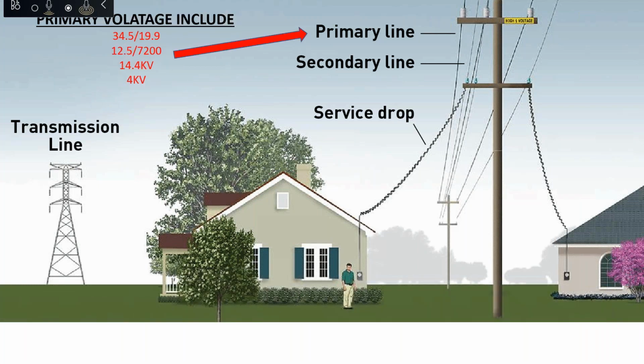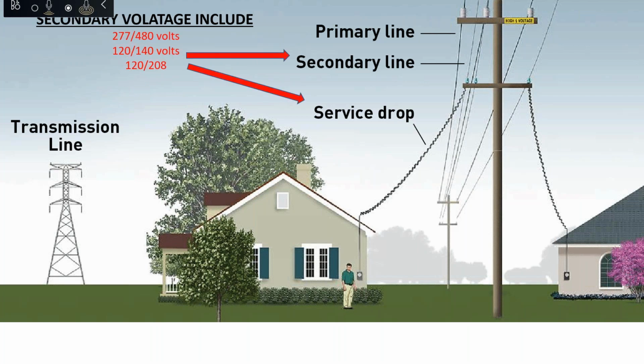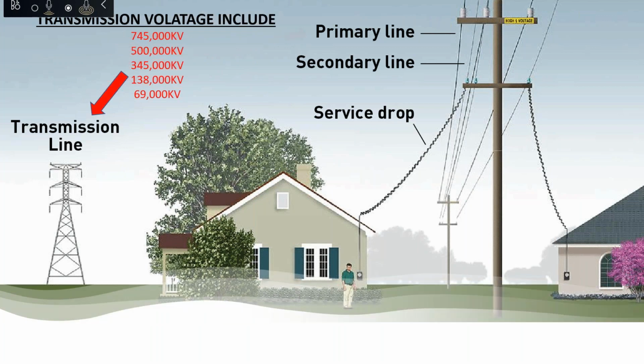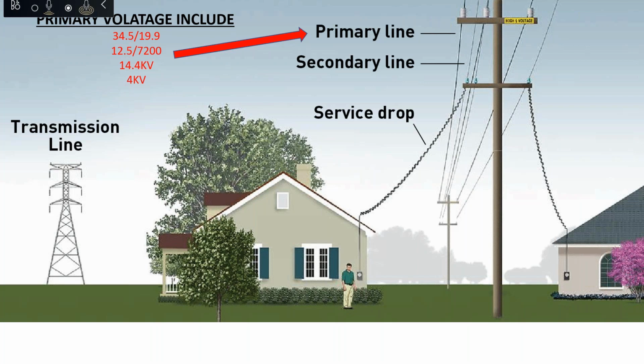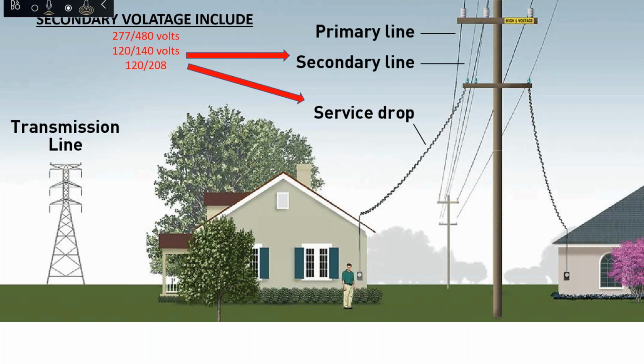But when we get down to our distribution voltage for our primary, 34.5 and 12.5, there's a lot more amps on that line. Amps are really the dangerous thing about electricity that we want to prevent anyone from coming in contact with. Now, when we go a bit further into what actually feeds the facilities — whether that's OG&E, PSO, or any other electric utility — we have a job of stepping that down from this large voltage of 745 or 138 down to 12.5 or 34.5, all the way down to something you can actually use.